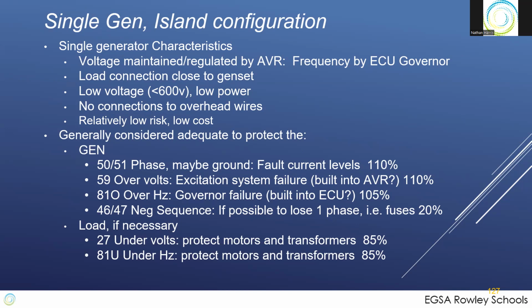Single generator, because voltage by the AVR, speed by the governor, load connection close to the genset, low voltage, low power, no wires. So typically, if you do 50-51 at 110% of rated, you'll be okay. So this is your overcurrent protection to 110%. Over voltage protection, again, 110%, you'll be okay. 81O, that's over frequency protection. Again, 105%, you'll be okay on that.